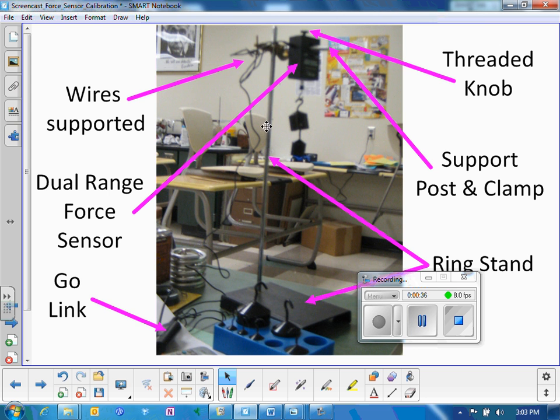The wires are supported on the clamp so that the sensor is free to hang vertically without having the wires drag it to one side or the other. Notice there's a threaded knob on the top. That knob is not tightened at all. It's just adjusted a little bit, so that the sensor is still free to swing back and forth from side to side. It's not locked in position. So do not tighten that threaded knob.